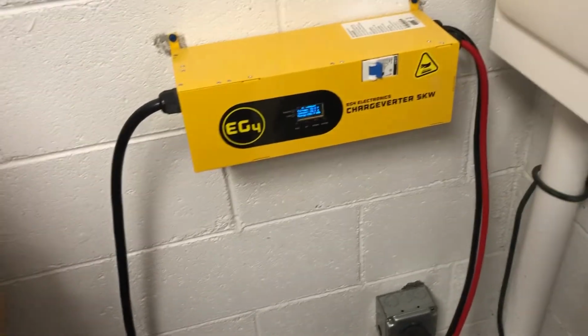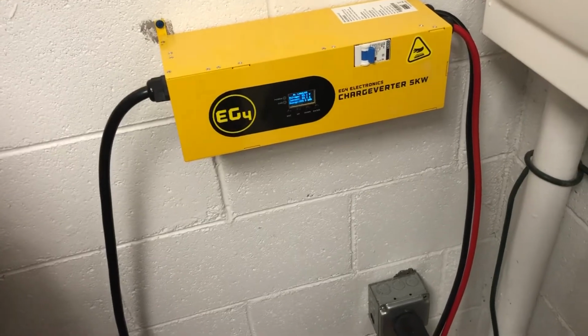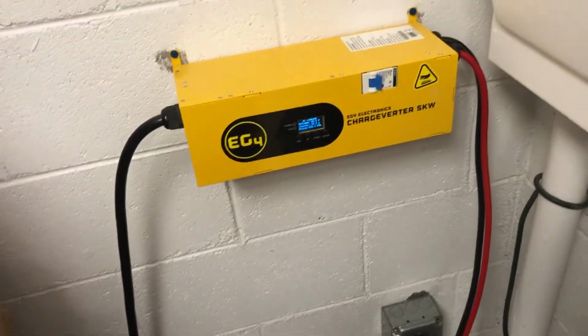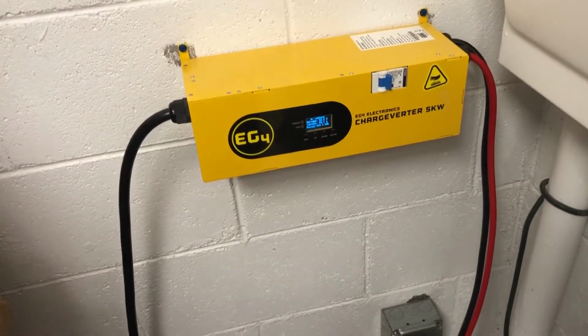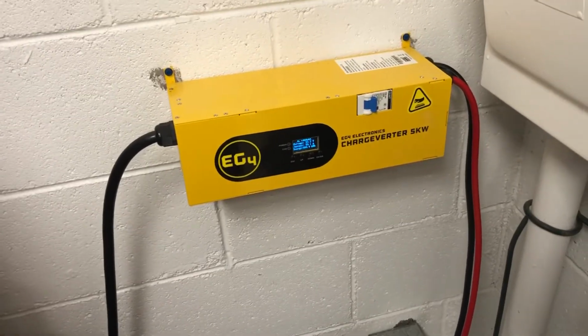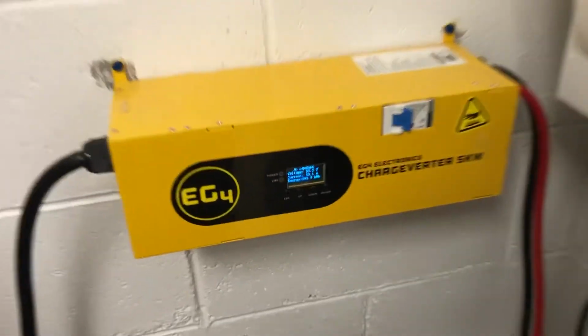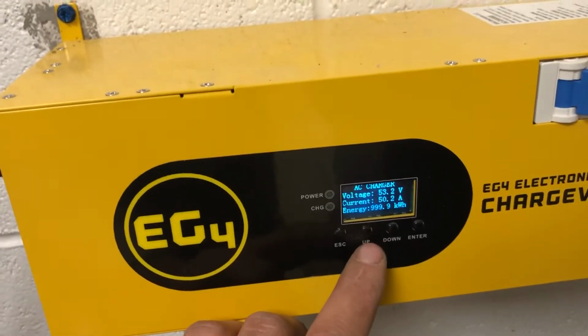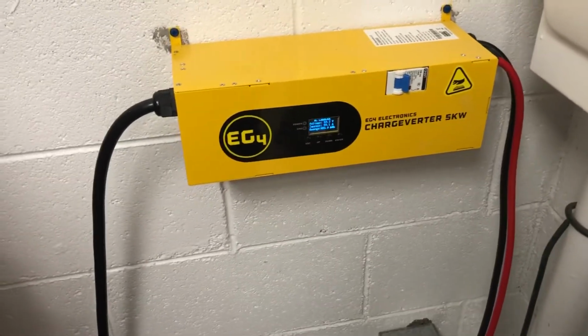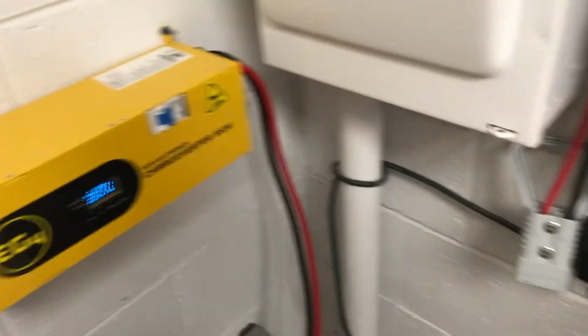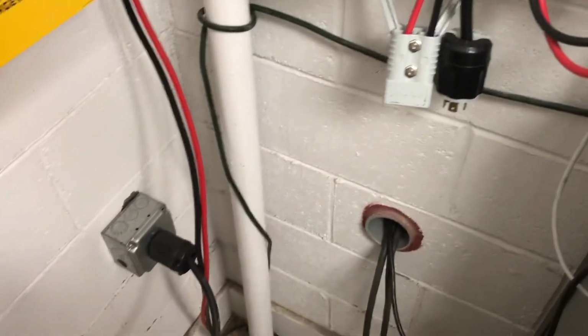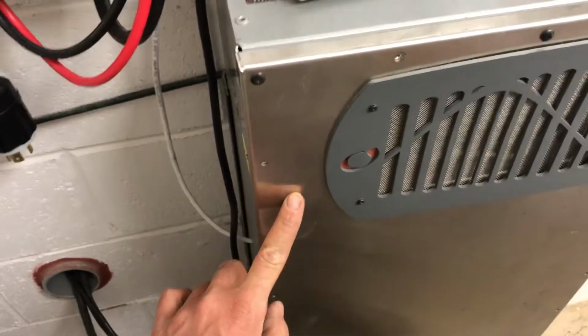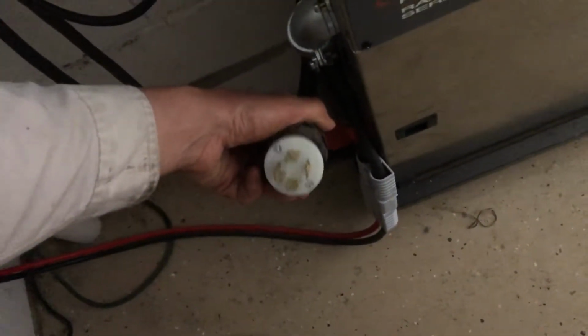This property was drawing about 47 kilowatt hours a day, and that's way less than 12 amps 24/7 can supply. So we haven't had any problems. You can see its output over 1,000 kilowatt hours. That's the max the meter does. And I just set the voltage for the float voltage of the batteries, and it's a 30 amp twist lock. This inverter has a 30 amp twist lock AC input as well for the grid.